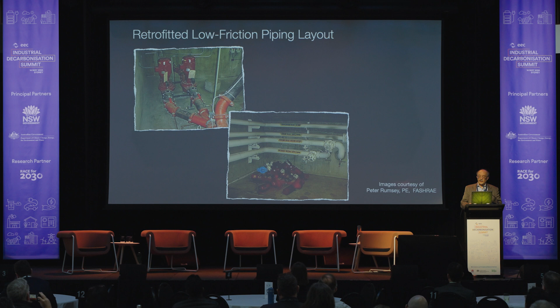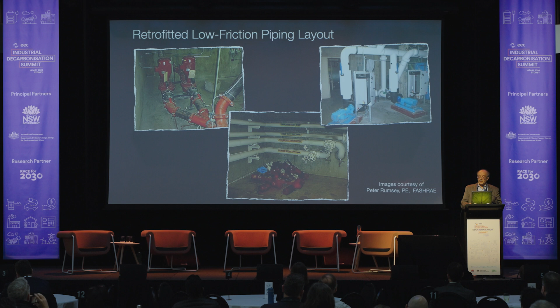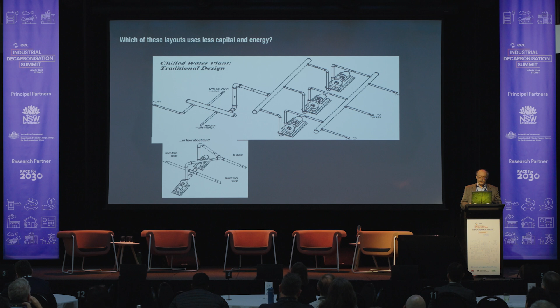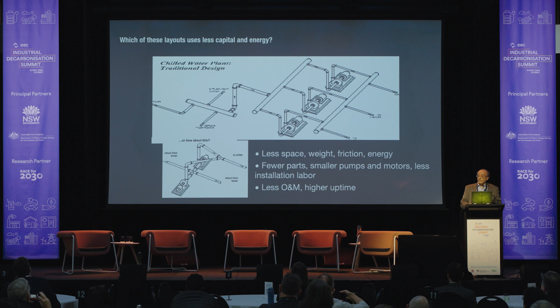I love negapumps. And then repiping the chilled water loop and adding variable frequency drives doubled the flow and saved 85% of the energy. Here's how we normally lay out in big buildings the piping of cooling tower water back to the chiller's condenser. But if we lay it out instead the way Rumsey does, everything gets better. Why don't we all do this? Just force of habit, bad habit.